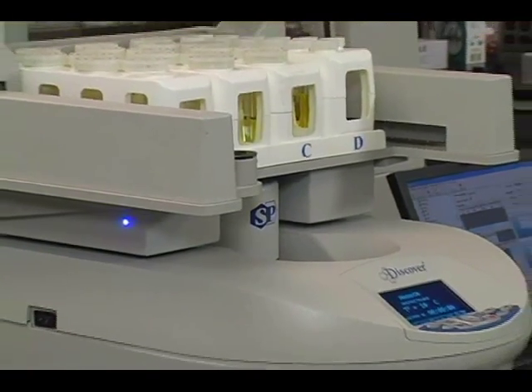Airflow increases as the digestion program ends to ensure a rapid cool-down time of around 2 minutes from over 200 degrees. Total time for the whole digestion process is 10 minutes or less including cool-down.